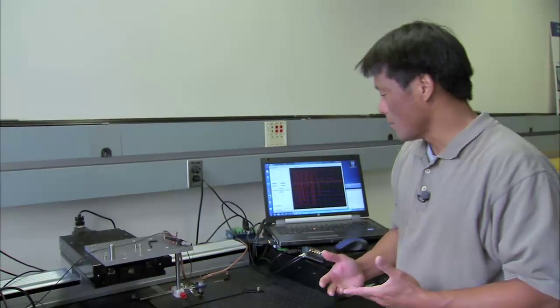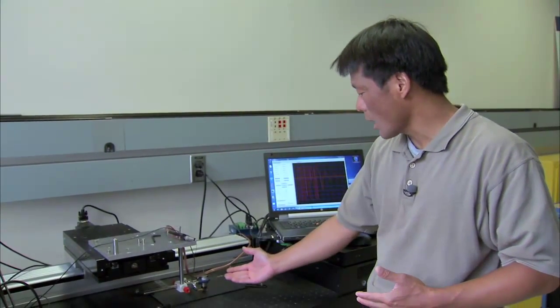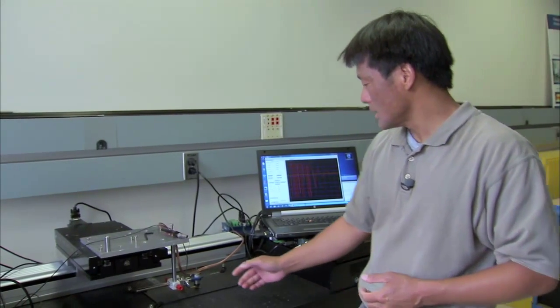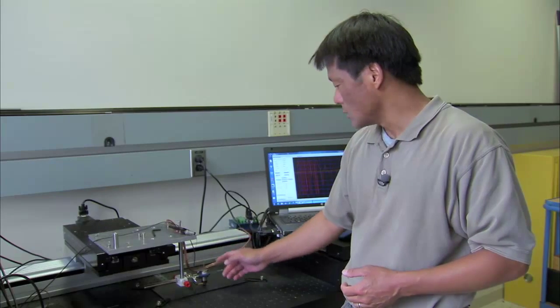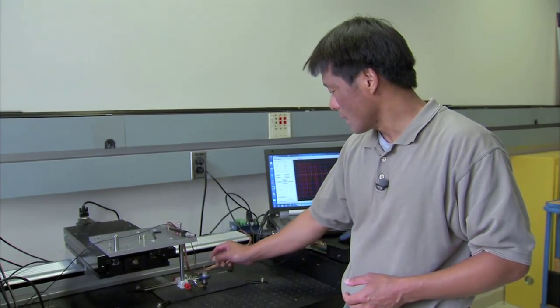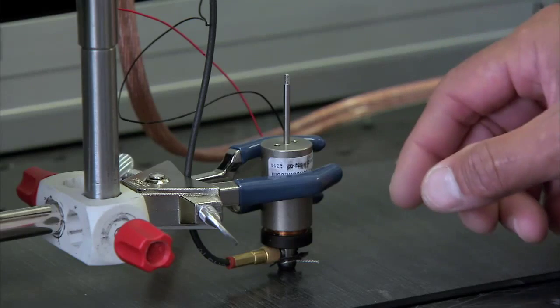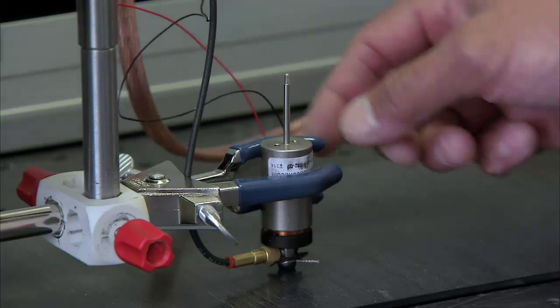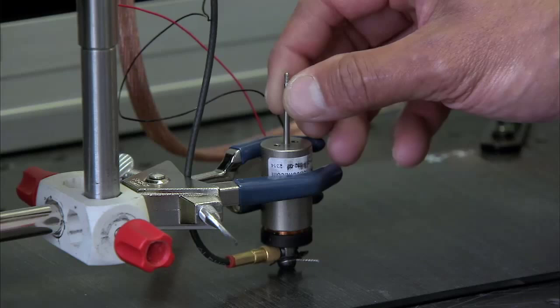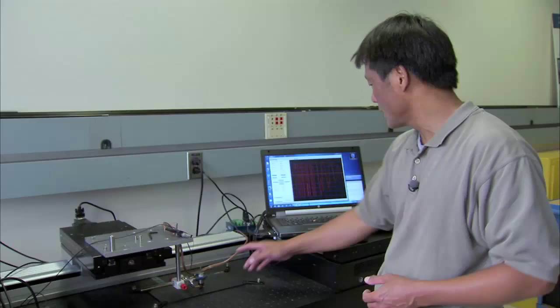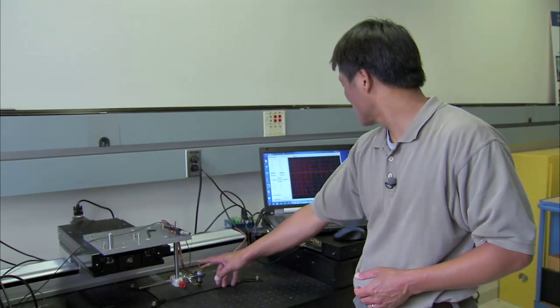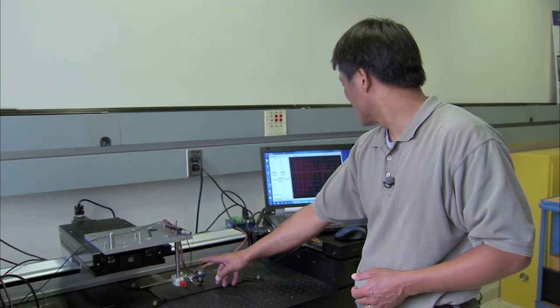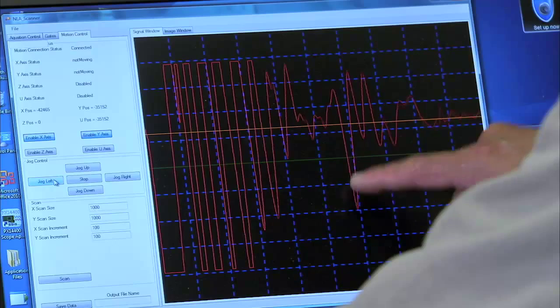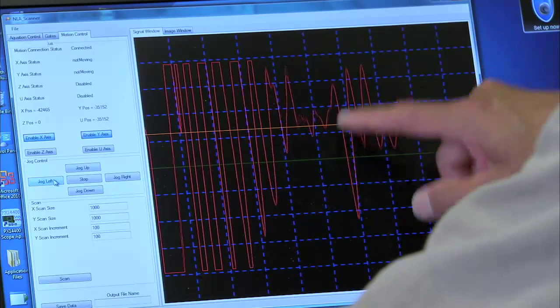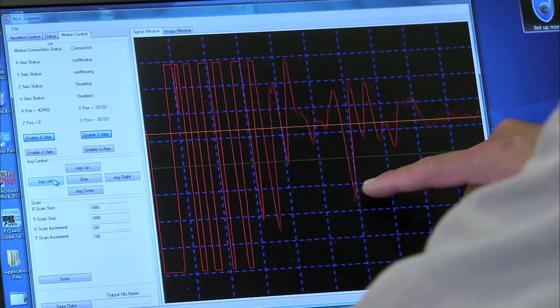So now we have the transducer with the solid couplant membrane mounted to a voice coil motor, and what that does is applies slight pressure, because it has a magnet in the coil. It can move. As I send electrical current to the motor, it can move this up and down. And as you can see on the screen here, as I slightly push down, you can see the waveform here, this signal here, which is the back surface of the composite sample that I'm inspecting.